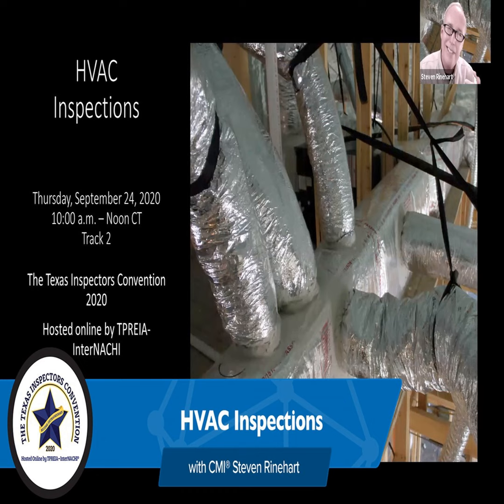Missing or deficient refrigerant pipe insulation, always an issue outside. Weed eaters chew up all the insulation on the low pressure line. If you got a crawl space house, it needs to go all the way to the unit. Hopefully if it's in a wall, it goes insulated in a wall. If it's in an attic, it should be insulated. Only thing that happens in an attic is typically mice will chew it up to get to the pipe so it'll sweat and make a water source. And you go up there and you see little pieces of black insulation all over the floor. You got two issues.